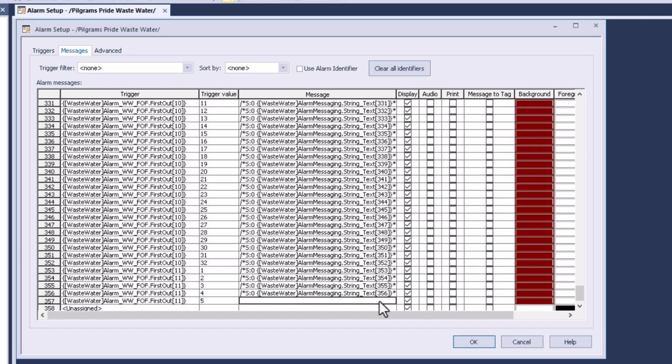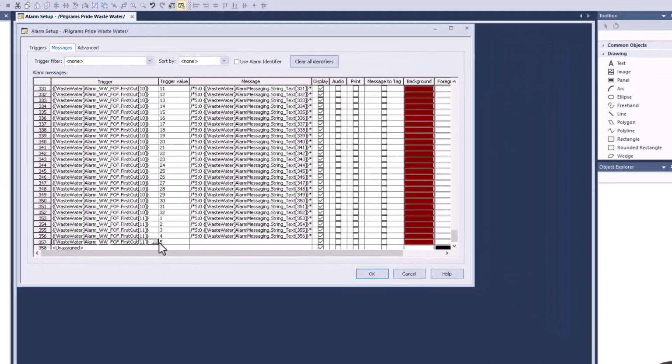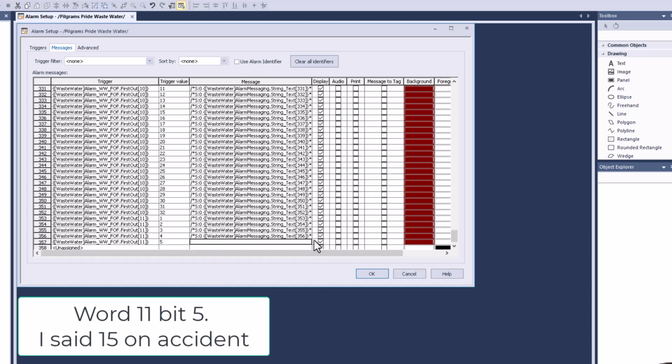Now that's done through the HMI. So you don't have to do that through your PLC. That communication path, that communication trigger point will automatically read from that string when that trigger happens. So when trigger 11:15 happens, it will automatically pull the string that I put in here. You don't have to have any PLC logic for that, okay? So just keep that in mind.